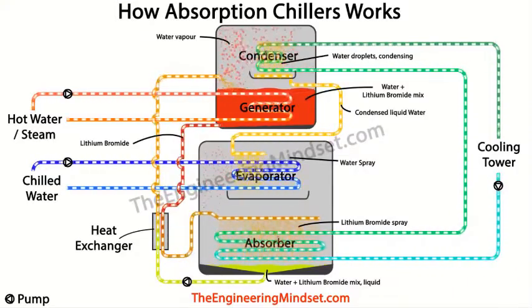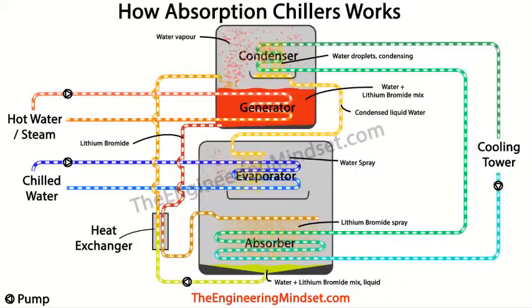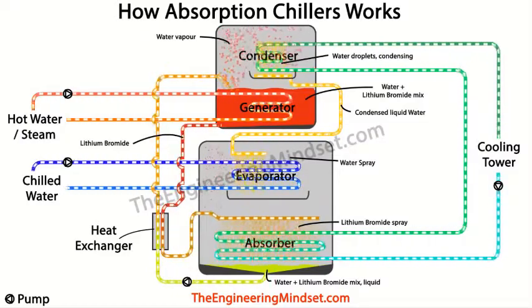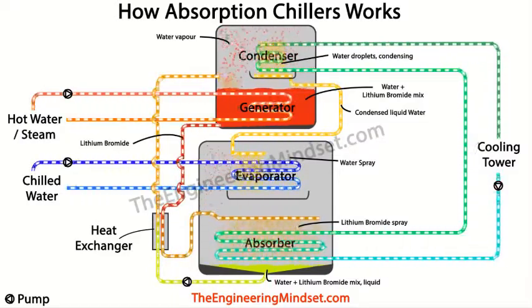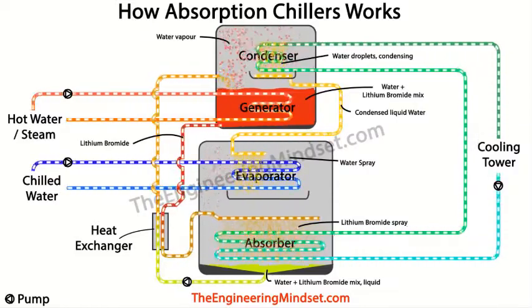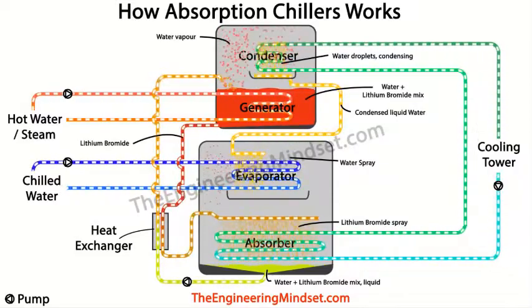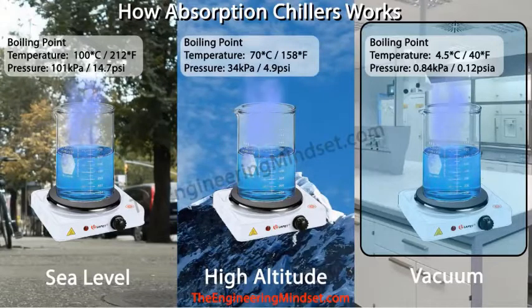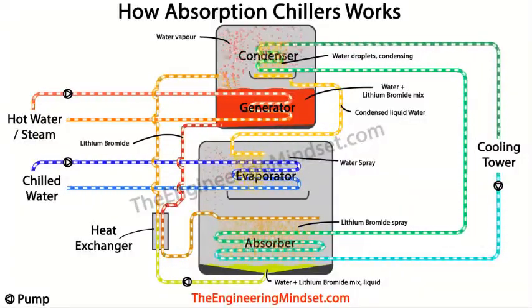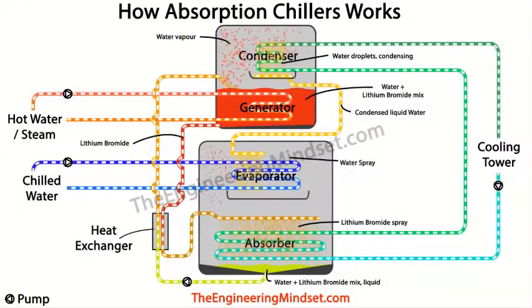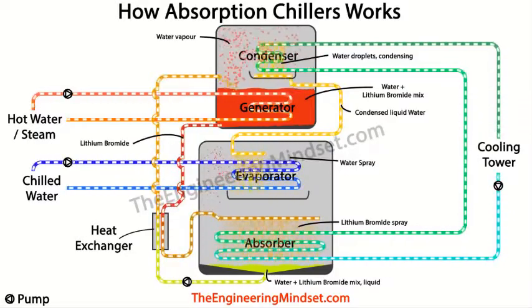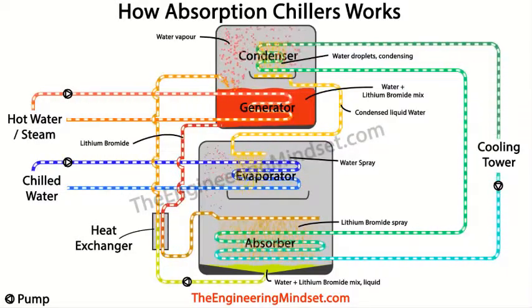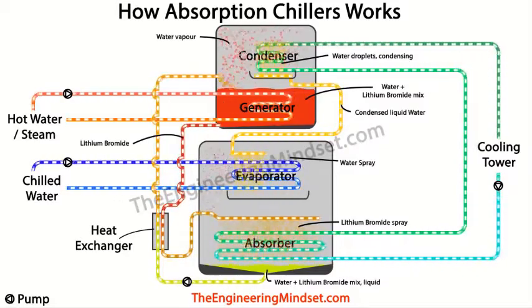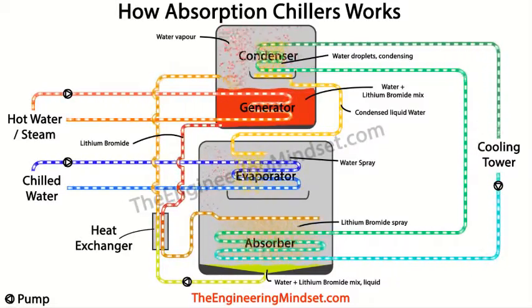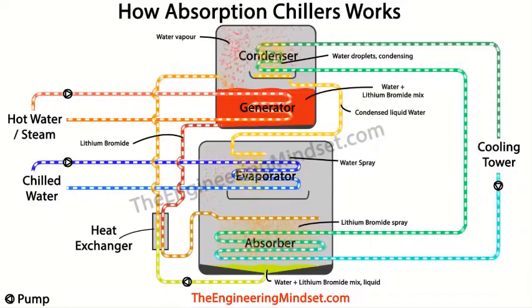As this heat transfers into the water on the outside of the tubes, this outer water will evaporate into a steam or water vapor due to the low pressure of the chamber. As it evaporates, it carries away all the unwanted heat with it. And remember, earlier we did learn how water boils at lower temperatures under low pressure. So the chilled water circuit has now given up all the unwanted heat, and by the time it leaves the chiller it should be around 7 degrees Celsius, which is approximately 45 degrees Fahrenheit, and this water is now ready to be pumped around the building again to collect more heat and bring it back to the absorption chiller.